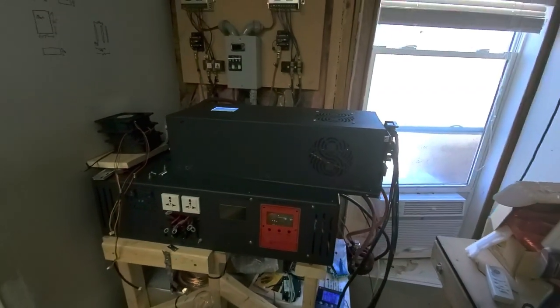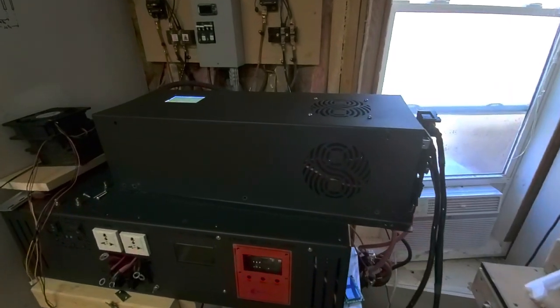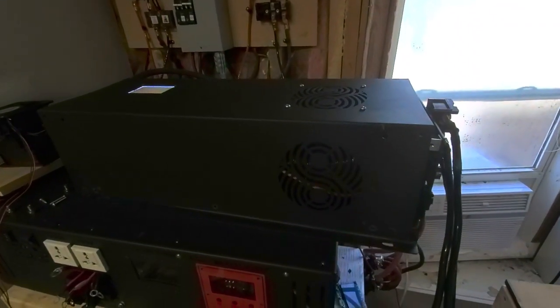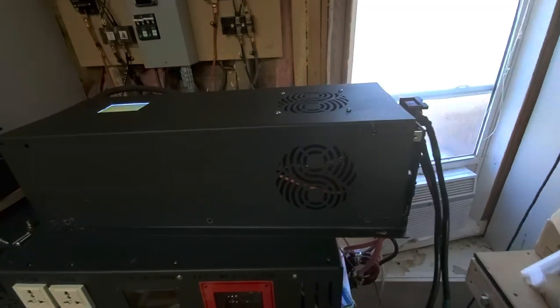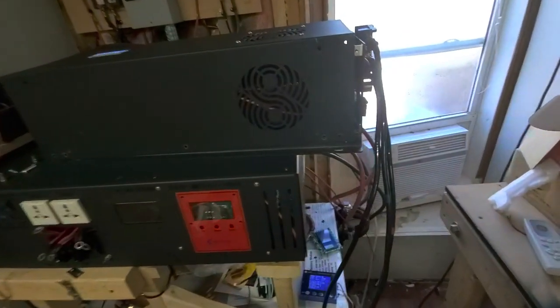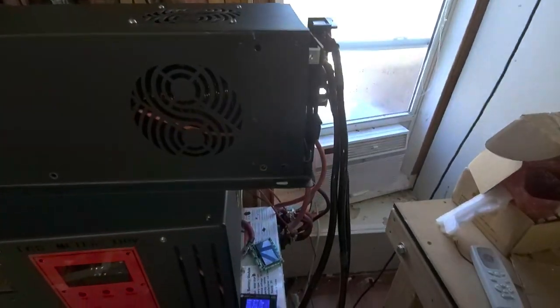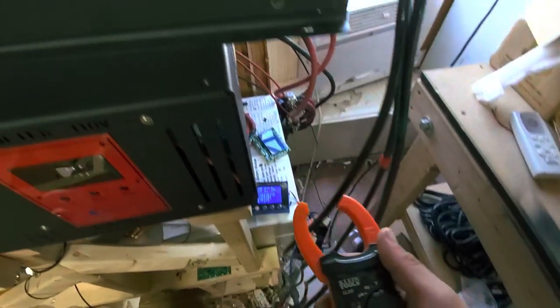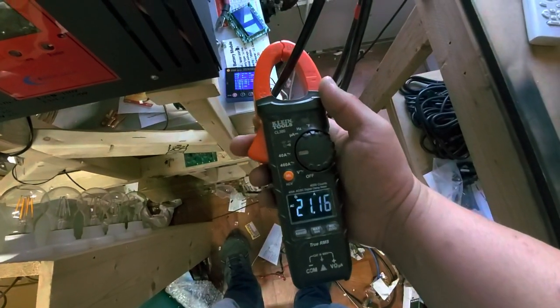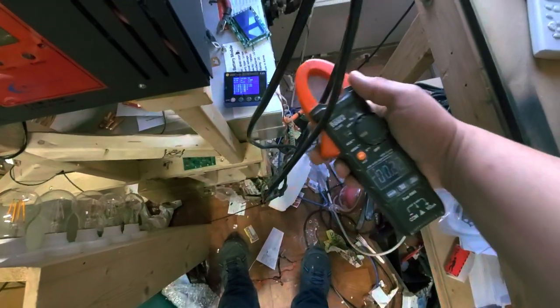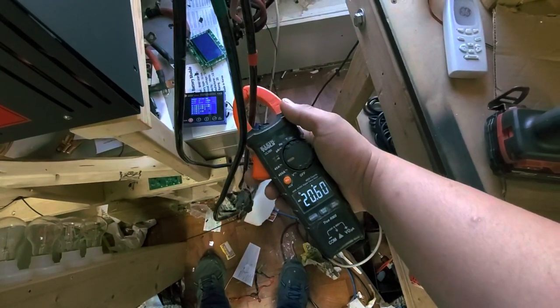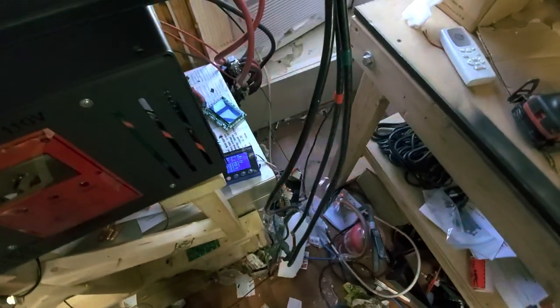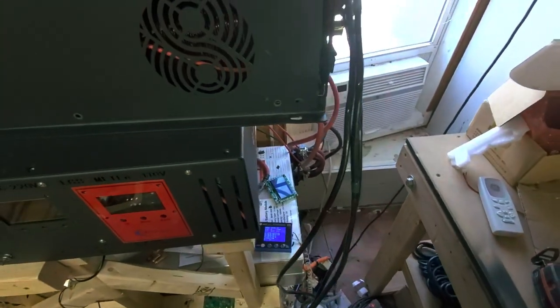Okay, I know it's hard for you guys to hear me. I'm currently doing a 5 kilowatt load test right now on this inverter. It's a true 5 kilowatt test. We've got 21.7 amps on L1 and 20.31 on L2, so yeah, I would call that 5,000 watts.